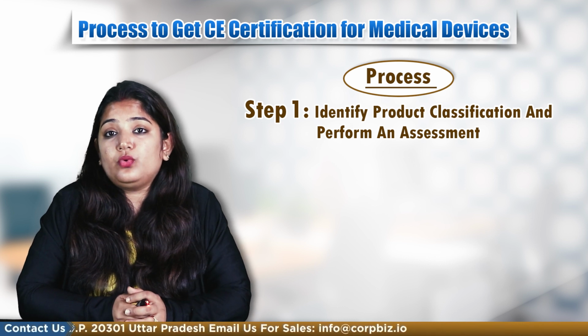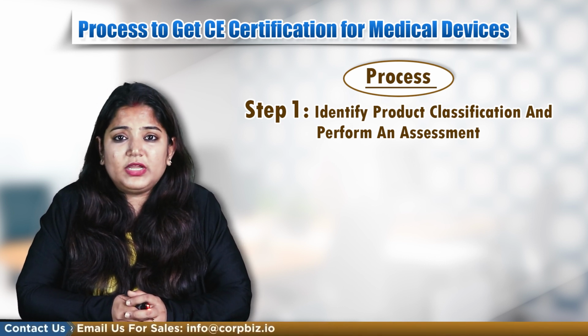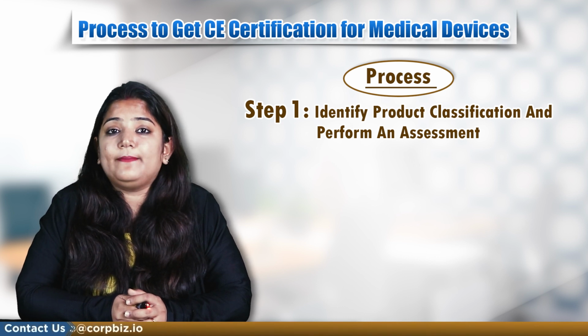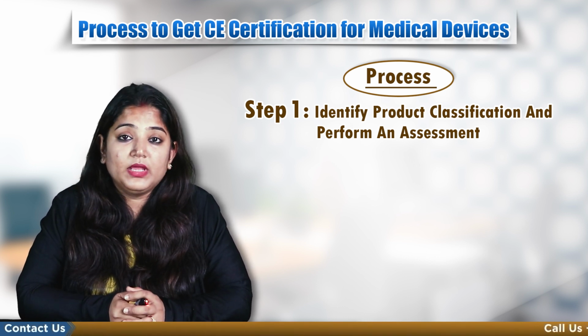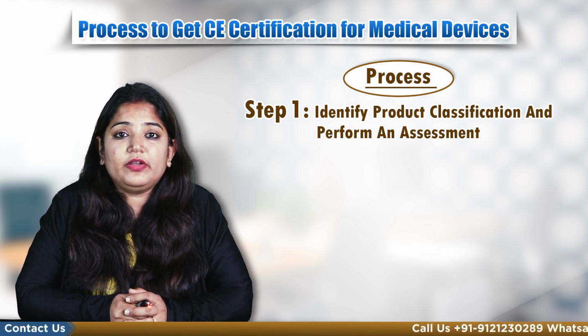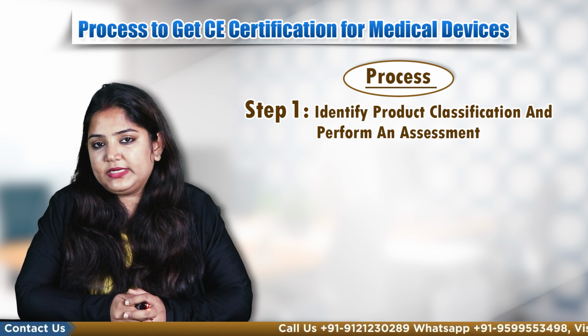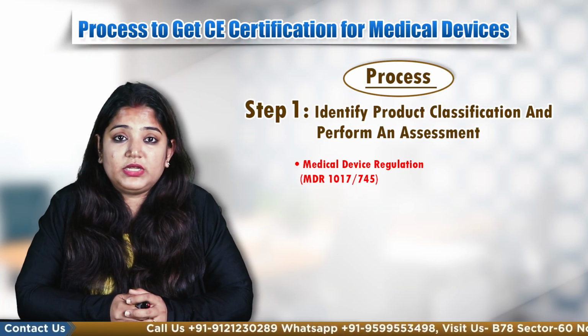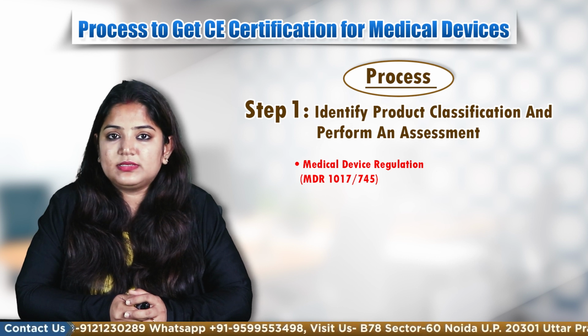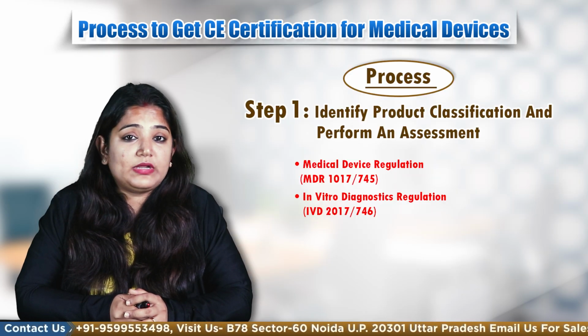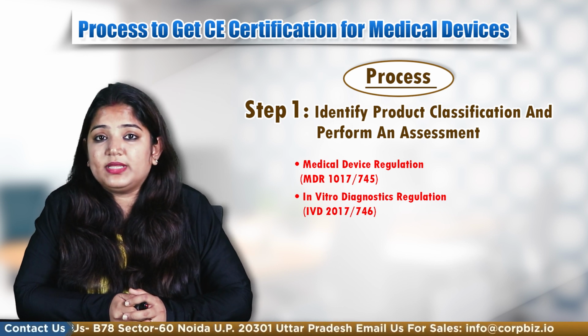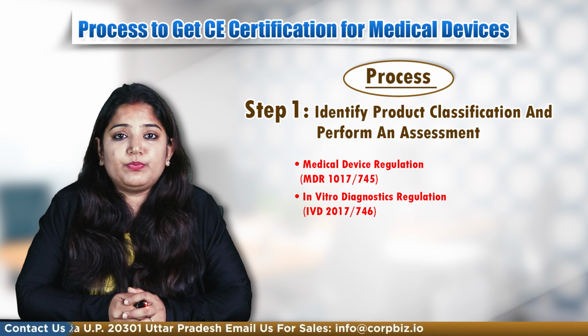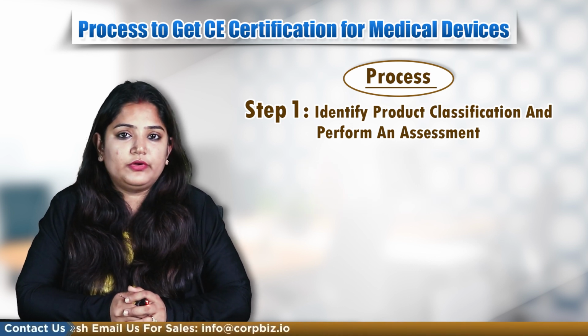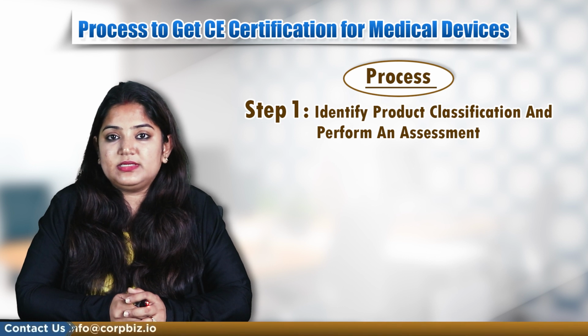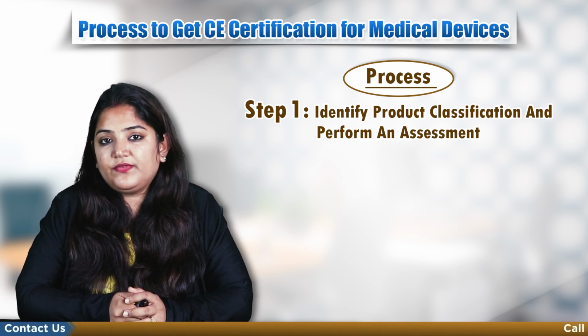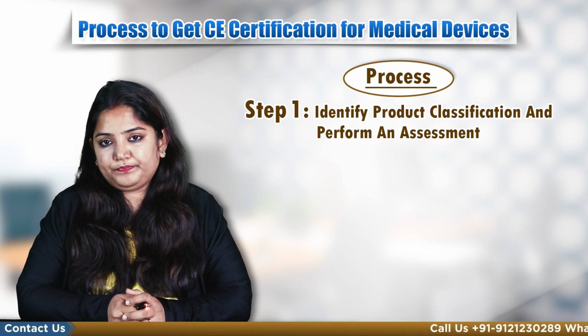To ascertain the product classification, it is important to figure out what type of regulation encompasses your device. Primarily, the following regulations are in force that govern the supply chain of medical devices. Medical Device Regulation, MDR, 2017/745. In Vitro Diagnostic Regulation, IVDR, 2017/746. As per European regulation, the applicant must refer to Annex 8 of the Medical Device Regulation to ascertain the product classification based on its risk profile.